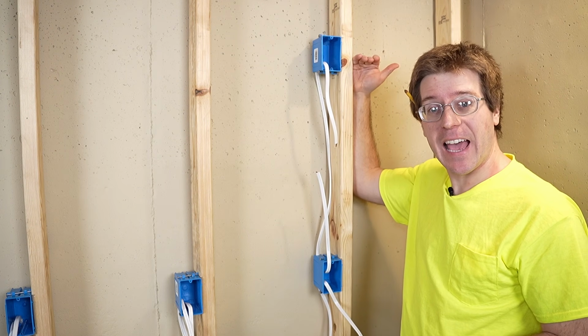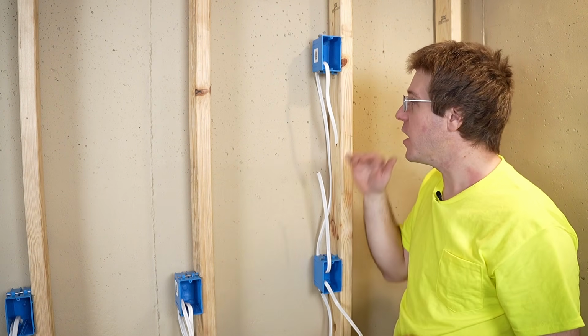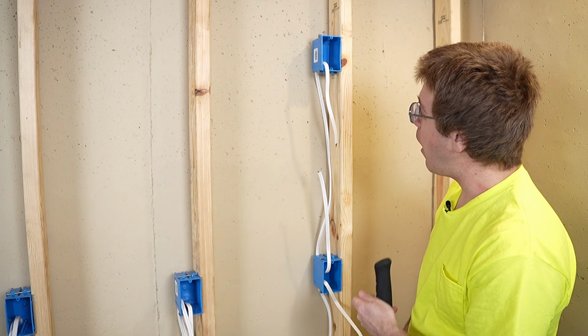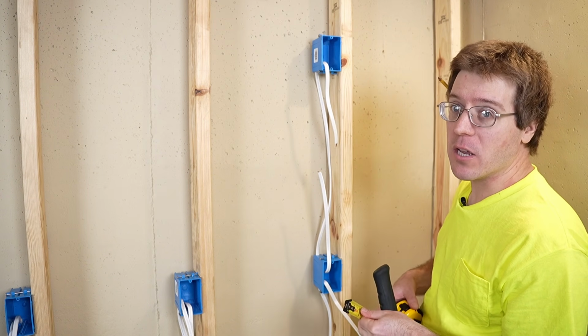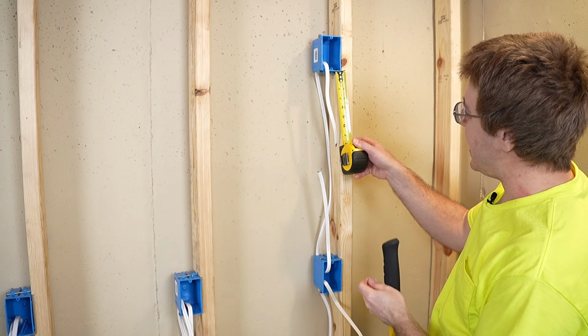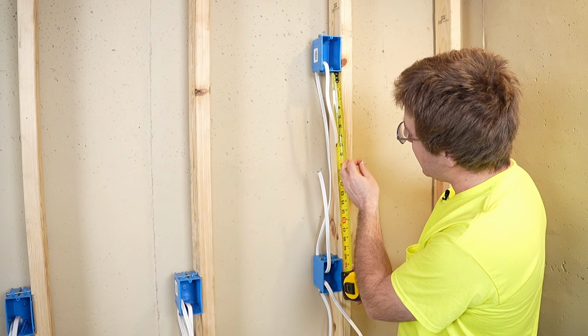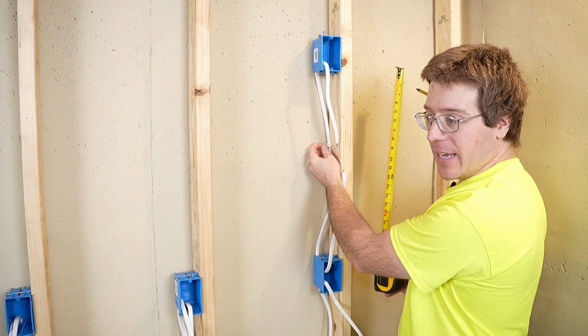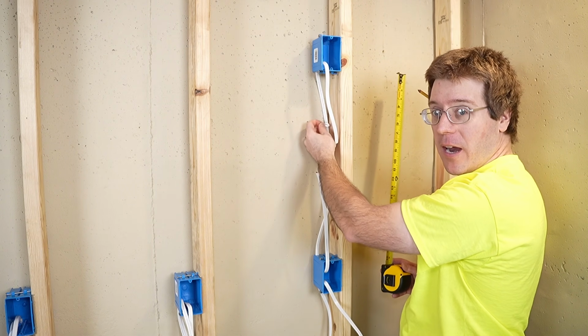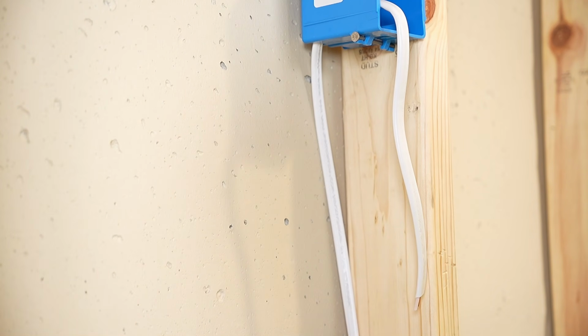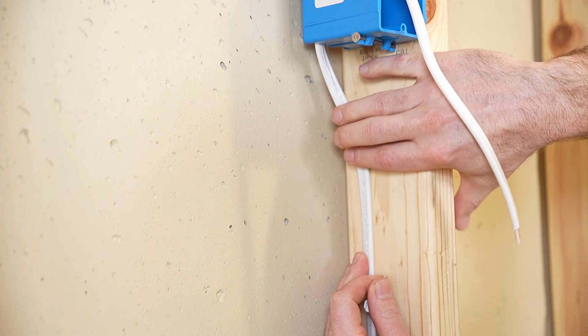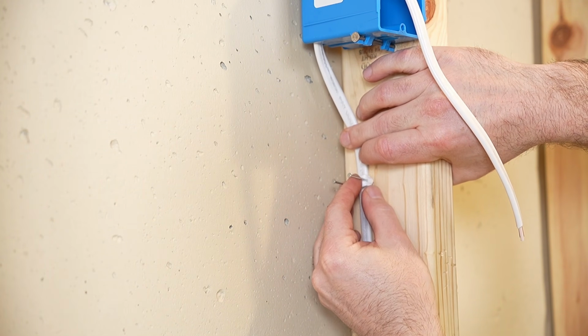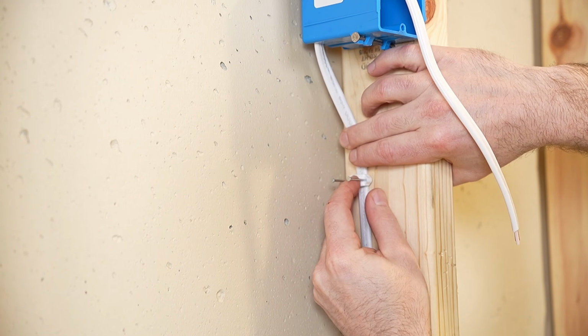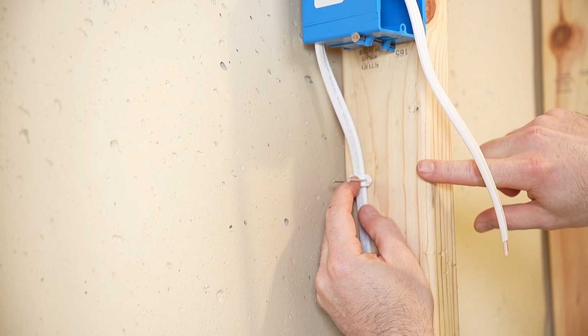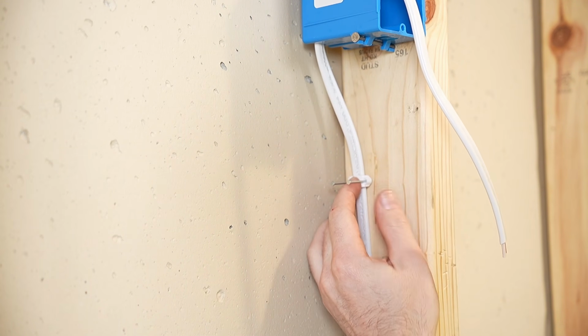Arbitrarily, I'm gonna start at the last box and work my way towards the panels, strapping the wire as I go. So outside of each one of these boxes, we have to put one of these staples within 8 inches. So in this case, we're gonna need a staple between here and here. Somewhere in there, we have to have a staple. As a beginner, you might have to measure these out the first couple times until you get the feel for where within 8 inches is. In this case, that's about what, 5, maybe 6 inches right here. I'm gonna go ahead and put my staple right here.